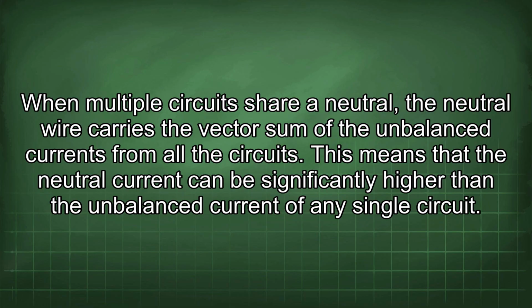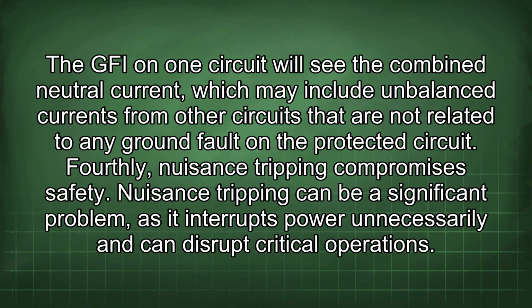When multiple circuits share a neutral, the neutral wire carries the vector sum of the unbalanced currents from all the circuits. This means that the neutral current can be significantly higher than the unbalanced current of any single circuit. The GFI on one circuit will see the combined neutral current, which may include unbalanced currents from other circuits that are not related to any ground fault on a protected circuit.